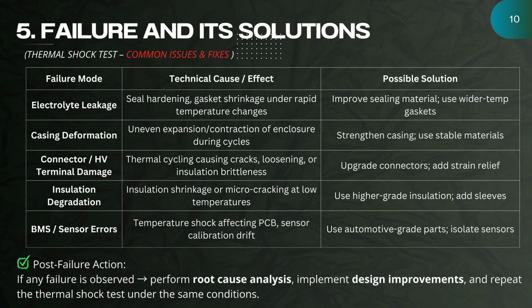This slide highlights some of the common failure modes observed during thermal shock testing and their possible solutions. Issues such as electrolyte leakage from gasket shrinkage, casing deformation from temperature expansion, connector damage due to cracking, insulation degradation at low temperatures, and BMS or sensor errors caused by thermal shock can occur. These are typically resolved by improving sealing materials, strengthening the casing, upgrading connectors, using higher-grade insulation, and adopting automotive-grade electronic components. As mentioned below, if any failure is observed, a detailed root cause analysis must be performed, design improvements implemented, and the test repeated under the same conditions.